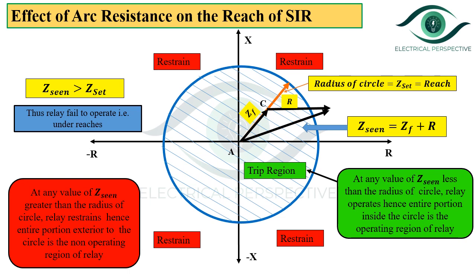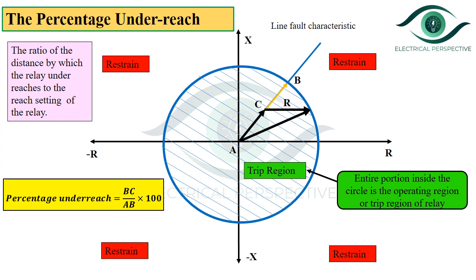We can say that arc resistance causes the simple impedance relay to underreach. The figure shows the characteristics of the simple impedance relay on the RX plane with the fault characteristics of the line superimposed. Considering an arcing fault with fault resistance R at point C, the impedance seen by the relay lies on the boundary between the trip and restraining regions. Thus any arcing fault just beyond point C will not be detected, confirming that the simple impedance relay under-reaches due to arcing faults.